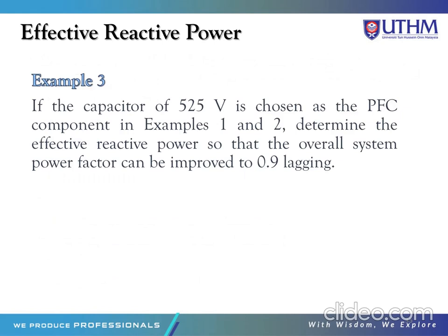This is example 3, effective reactive power. If the capacitor of 525 volt is chosen as the PFC component in examples 1 and 2, determine the effective reactive power so that the overall system power factor can be improved to 0.9 lagging.